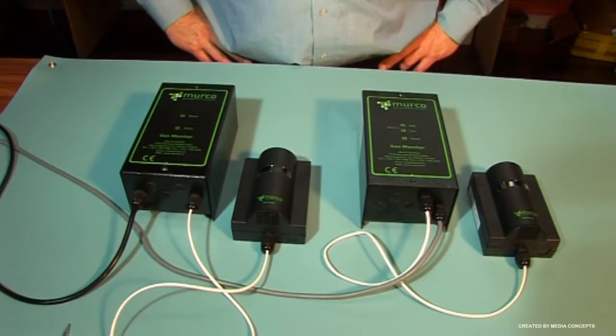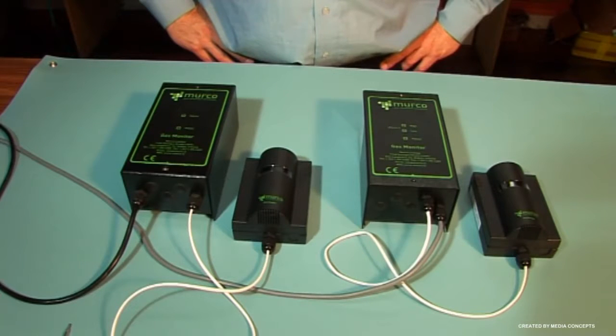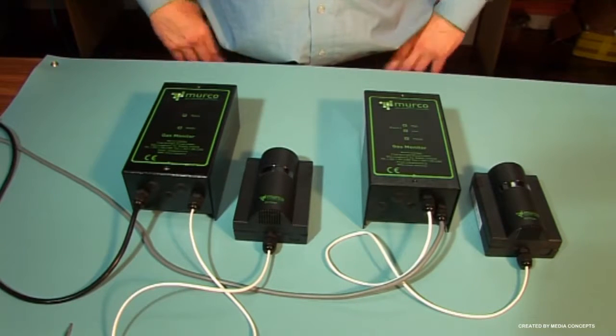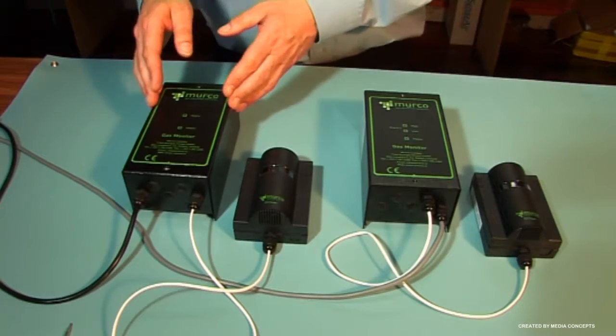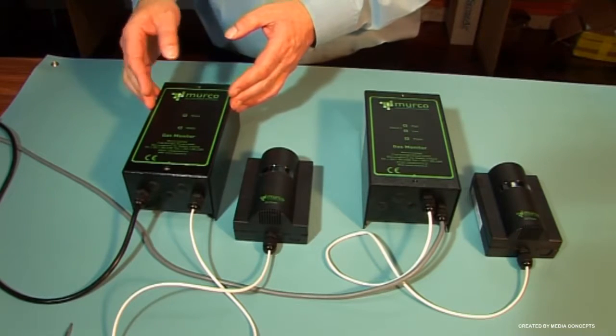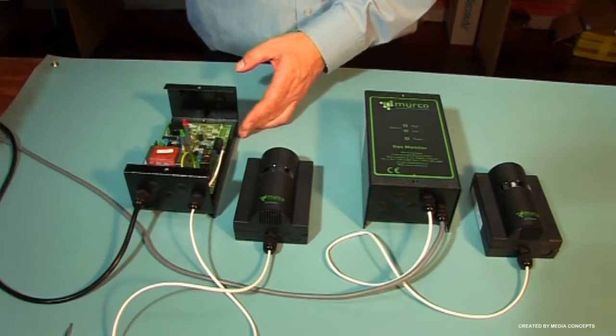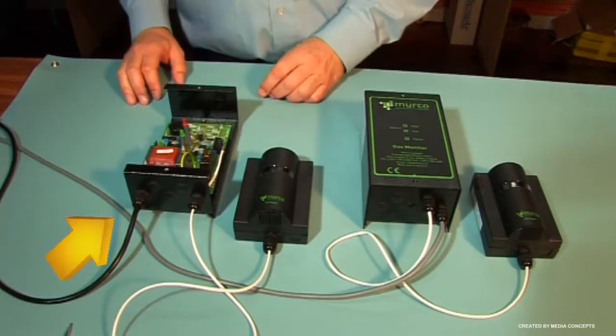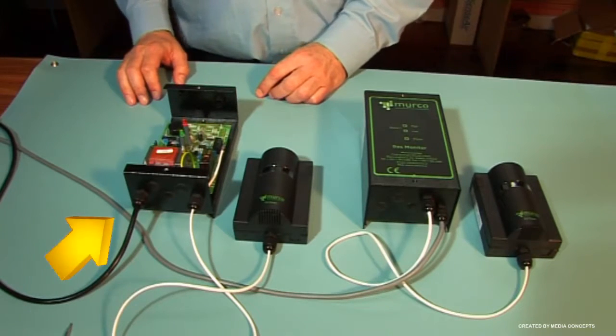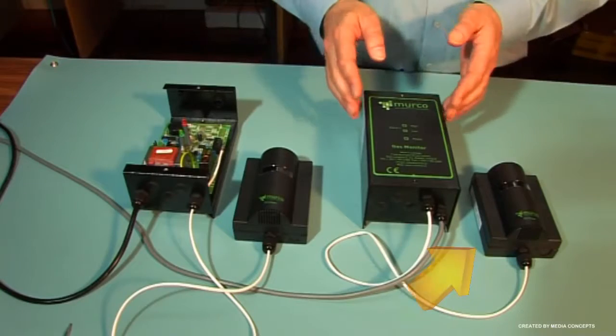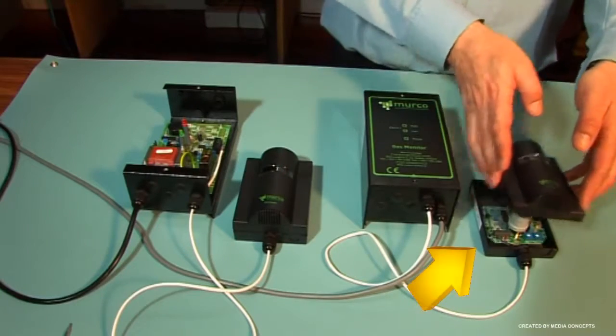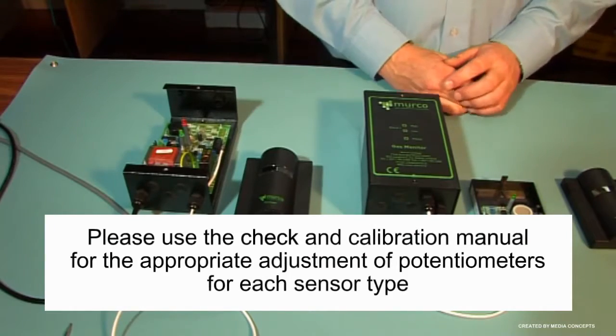This is the MGD unit. The MGD has models for 1 or 2 levels of alarm and can range from 1 to 6 sensors connected to the controller. On the 1-level systems, the calibrations are carried out on the controller, and on the 2-level systems, the calibration is carried out on the sensor. For demonstration purposes, we shall use a 1-channel unit for both the 1 and 2-level systems.